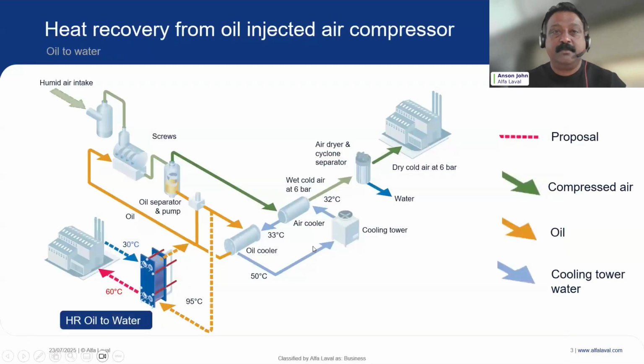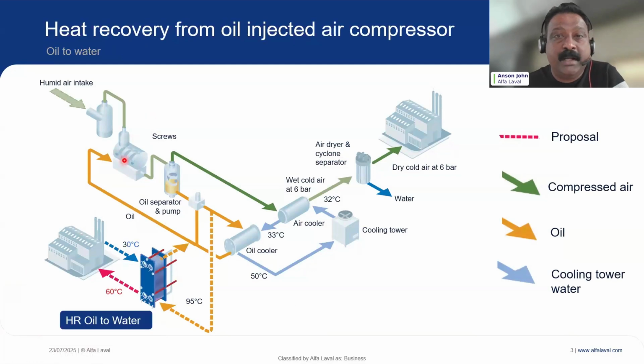So I would like to talk about a few applications where we are predominantly working in the food and beverage industry for recovering heat. And this is a typical example. If you would like to do heat recovery from hot oil in an air compressor, you can see in the schematic you've got a screw air compressor, which is producing hot air at 95 degrees C. Of course, it carries some oil, and that oil is separated in the oil separator. It goes to the oil cooler, then with the cooling tower water it is cooled, and that cooled oil goes back to the air compressor.